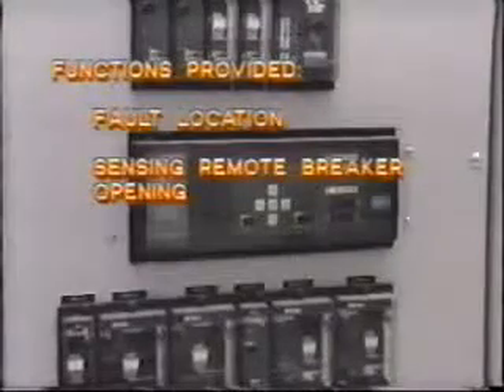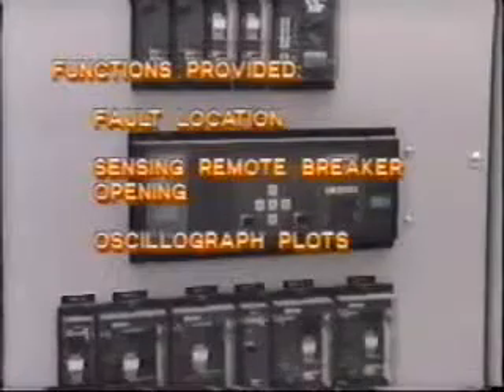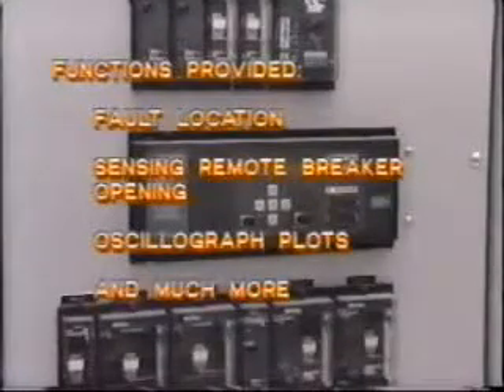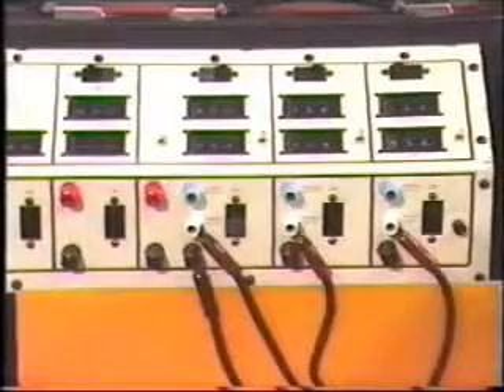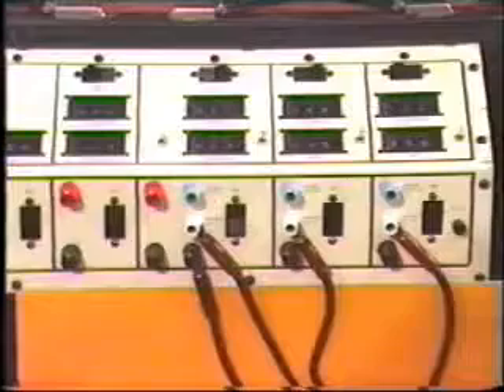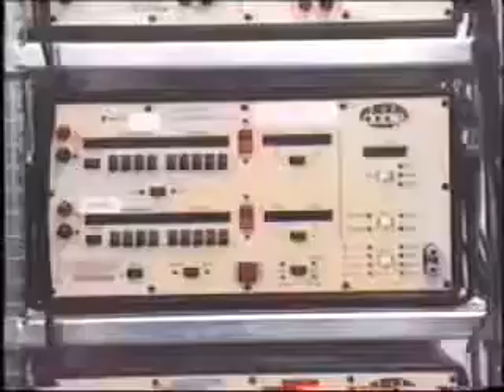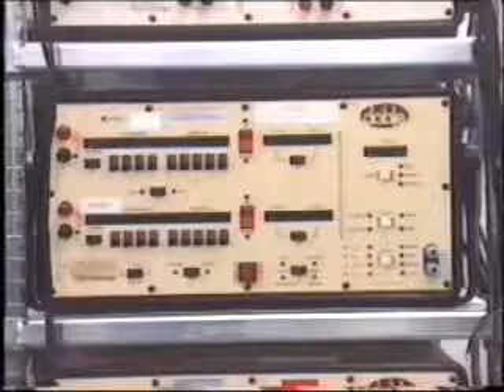In the 1980s, relay manufacturers began producing smart microprocessor-controlled relays which can perform many sophisticated functions beyond the reach of previous technology, such as fault location, sensing remote breaker opening without communications, oscillograph plots of recorded faults, and much, much more. Even solid-state test equipment could not exercise these relays to verify all of their functions. As we'd expect, relay test set manufacturers rose to the occasion and began producing smart microprocessor-controlled test sets. Most utilities are now using this type of testing.